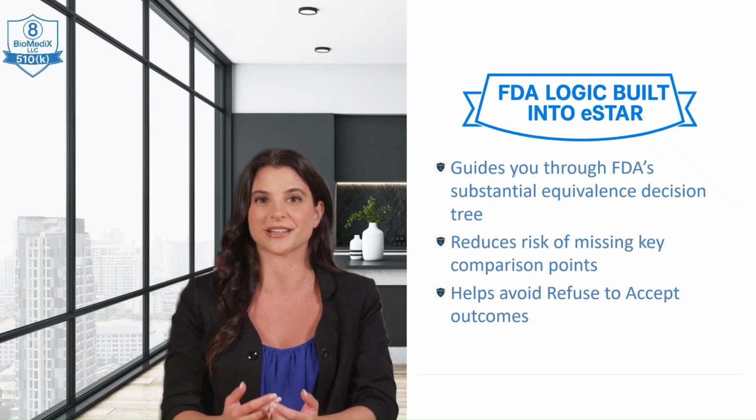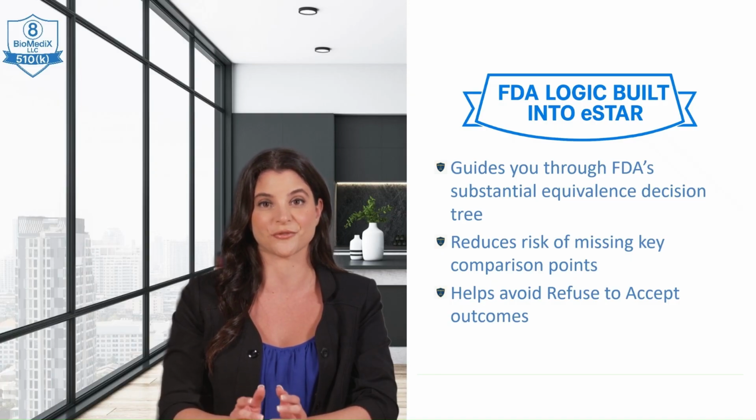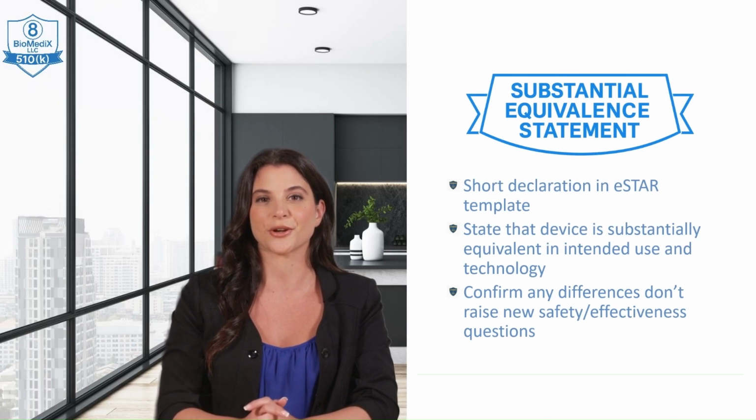Finally, you'll complete the section with a concise, substantial equivalence statement. This is your formal declaration, typically a short text box, where you declare that the subject device is substantially equivalent to the identified predicate device in terms of intended use and technological characteristics, and any differences do not raise new questions of safety or effectiveness.